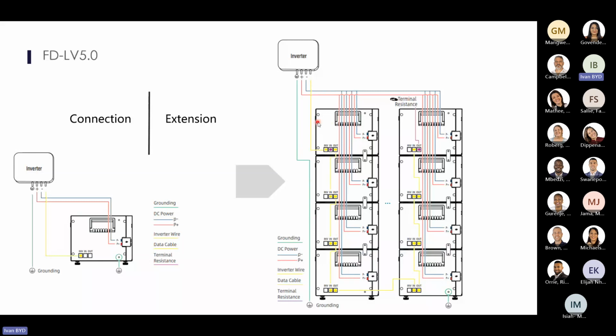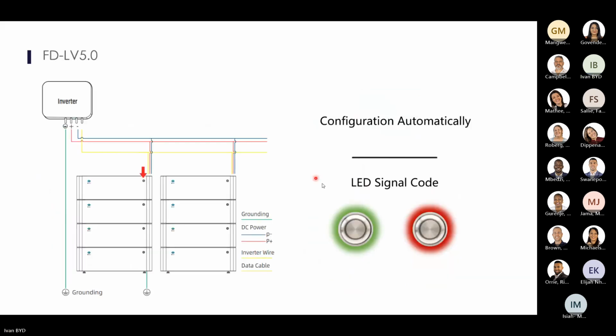In terms of wiring, no BMU is required for these batteries, and they are auto programming, so you don't have to commission them. So the inverter connects to the battery, and then the comms daisy chains from there. And there's the earth connections. It's always very important to have good earth connections. It stops any issues with communications.